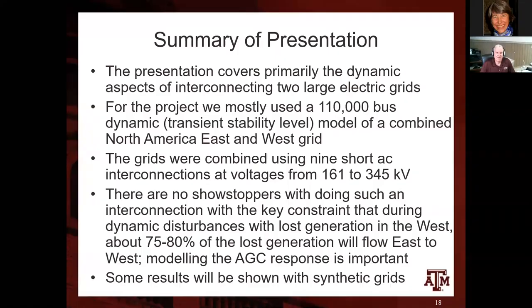The takeaway is we don't see any showstoppers with doing such an interconnect. The key constraint is that during a dynamic disturbance, if the disturbance is in the west, lost generation will quickly flow from the east into the west, across the interconnection. When I looked at the circuit diagram of the interconnection from 1970, I was surprised they didn't seem strongly interconnected. I thought, during a disturbance a lot of power would flow across those few lines, causing large angle differences, and they'd probably separate—and that's actually what occurred.